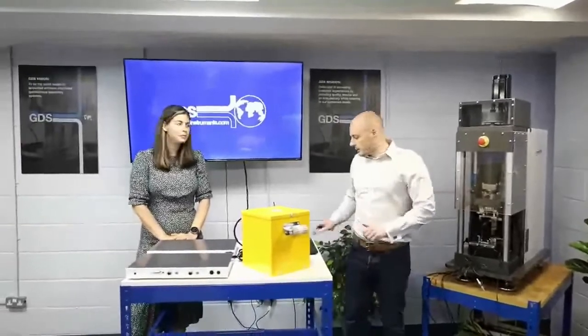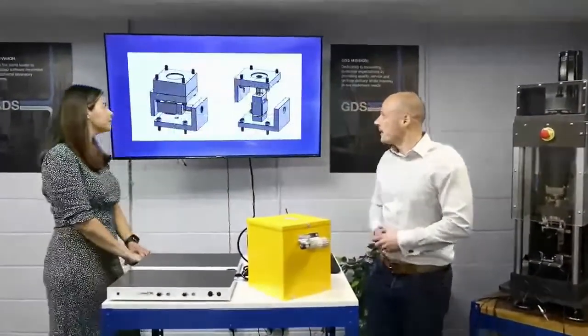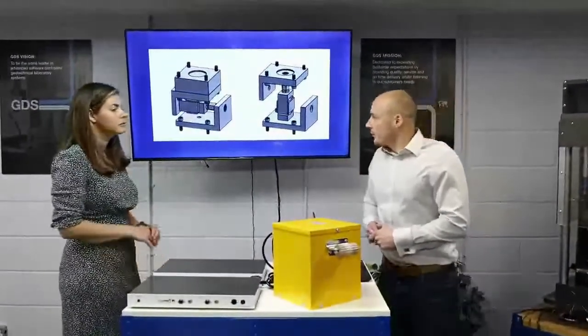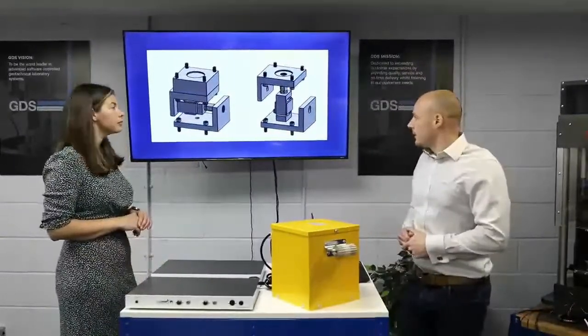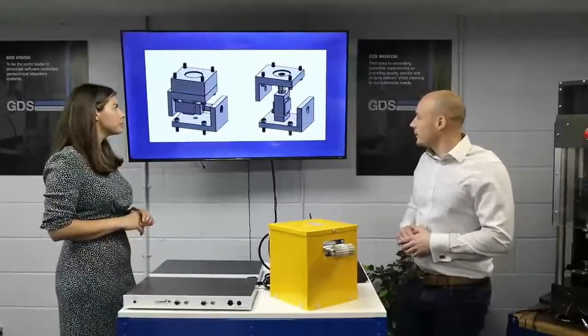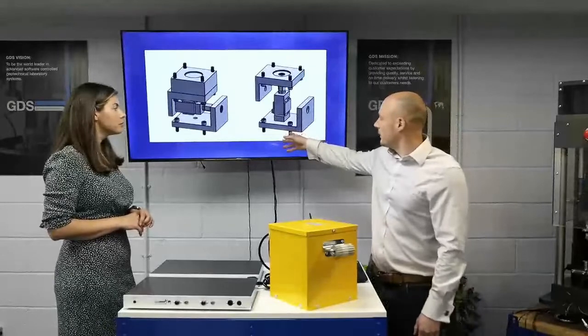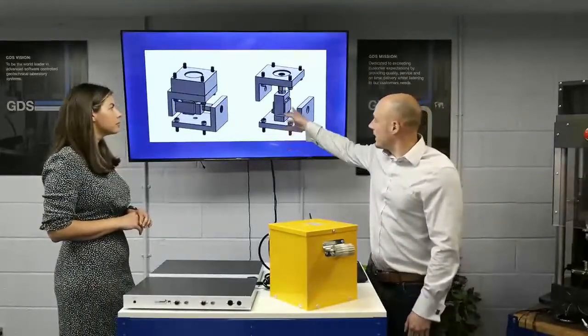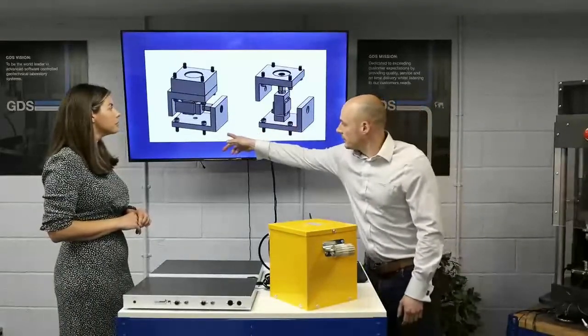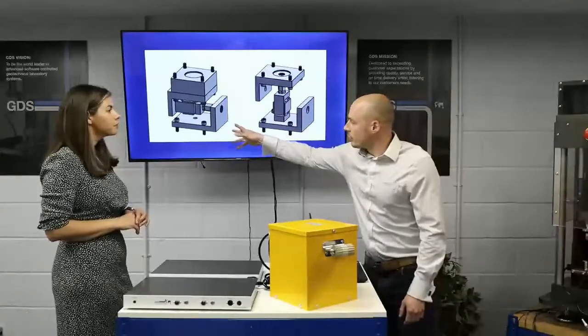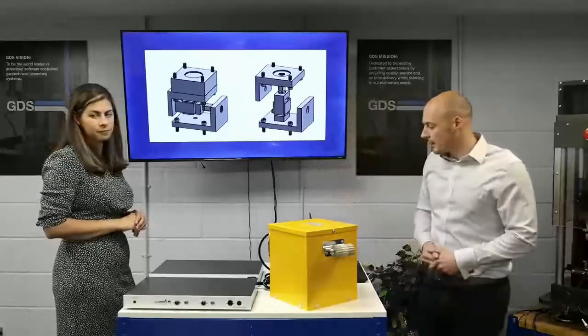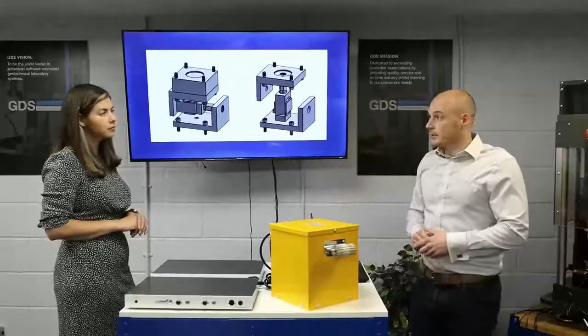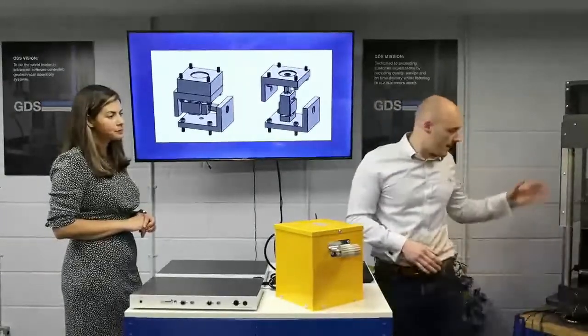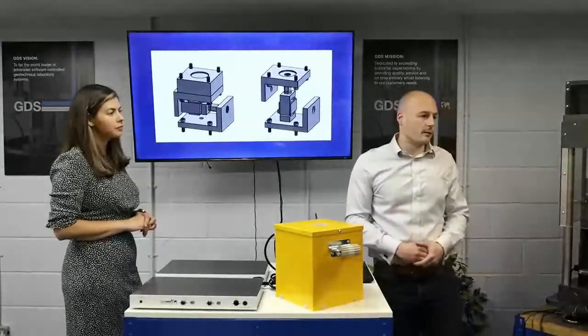For the load cells, we have a calibration jig. This fits in both orientations. The full kit can either be done in 5 or 10 kilonewton configuration. On the right hand side here, this is for axial load cell calibration. And then on the left hand side here, we can do both the primary and secondary shear load cell. We also do a calibration jig for the displacement transducers, and then again that can do all of the upgrade LVDTs as well.